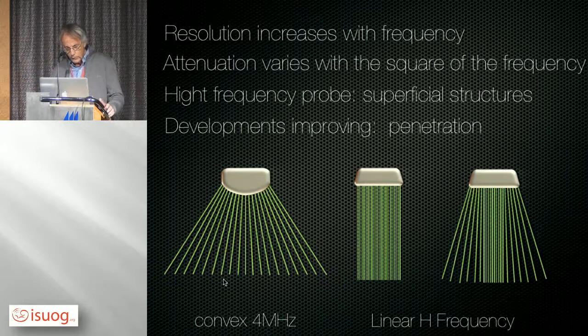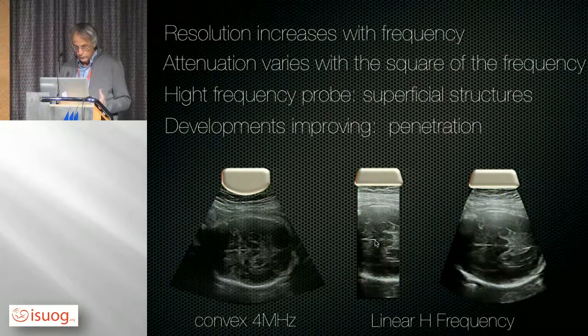When we use high-frequency probe, we will use linear probe, and the steering of the beam is parallel, and we have parallel line and with a really good resolution. Also, if it's necessary, we can steer oblique here, but in this case, the resolution will be less than in this case. And you have here the same head taken with a normal probe, with a high-frequency probe linear, and with a pseudo-convex.